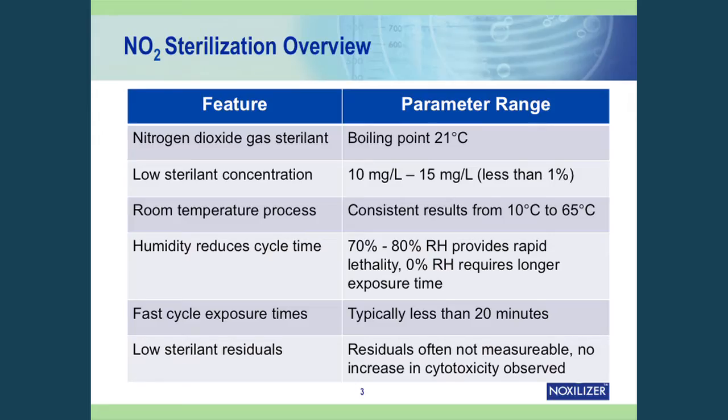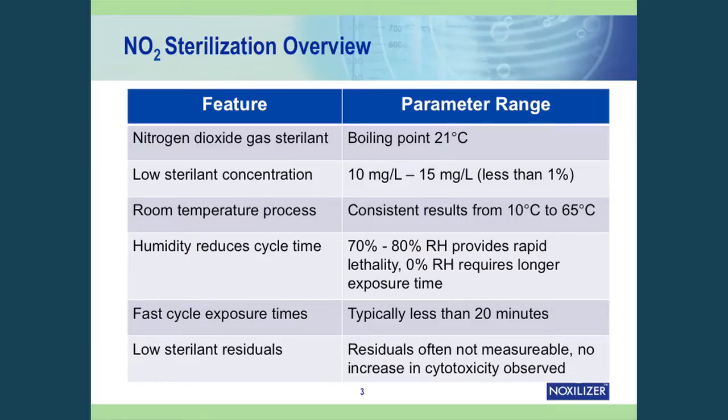As a background, nitrogen dioxide is a room temperature process and the sterilant nitrogen dioxide boils at room temperature. Because it boils at such a low temperature, it has a high vapor pressure and doesn't condense or collect on the surfaces of the medical products being sterilized. That leads to rapid off-gassing and efficient removal of sterilant residuals. We use a low concentration of NO2, typically less than 1%, about 10 to 15 milligrams per liter — significantly less than ethylene oxide, which would be hundreds of milligrams per liter.